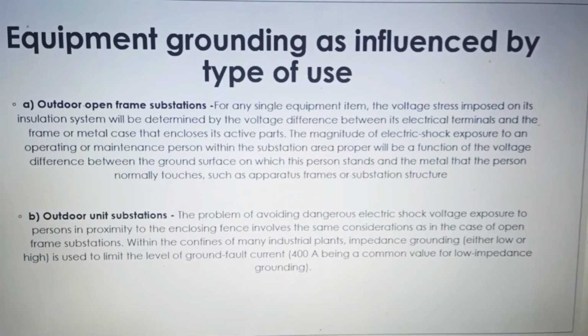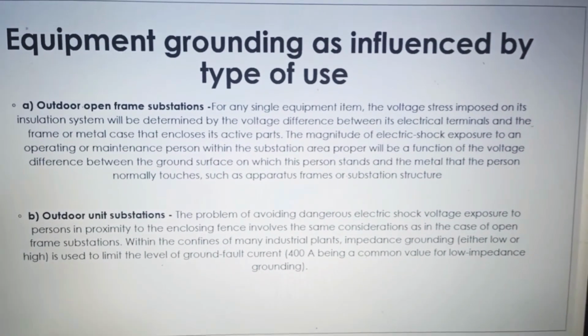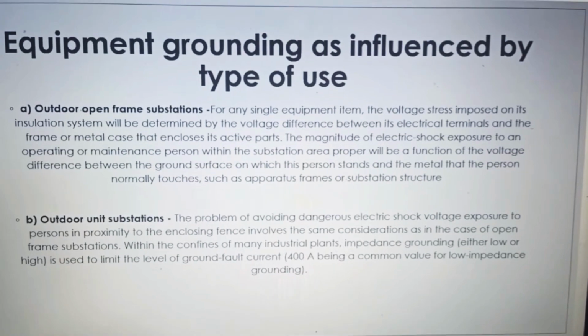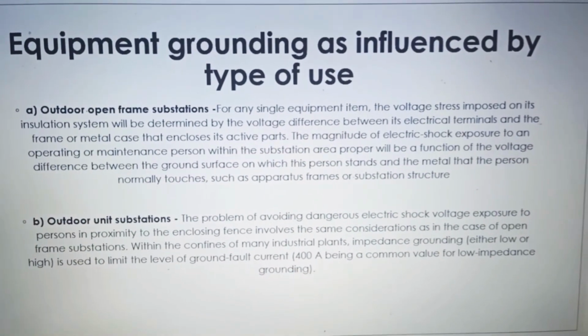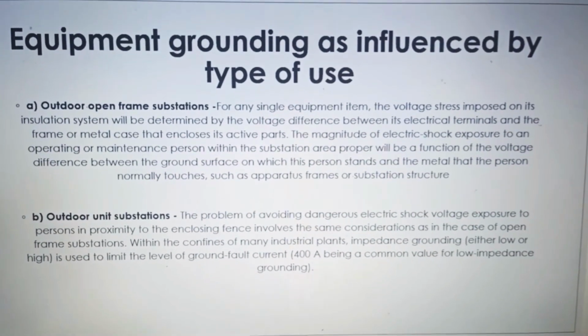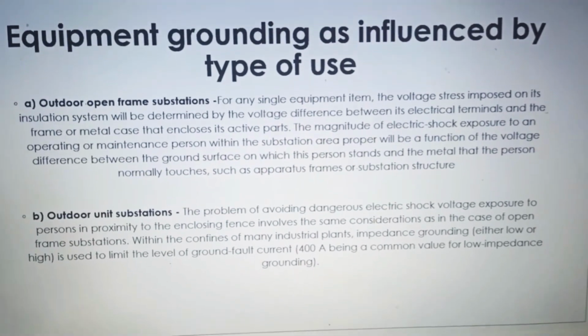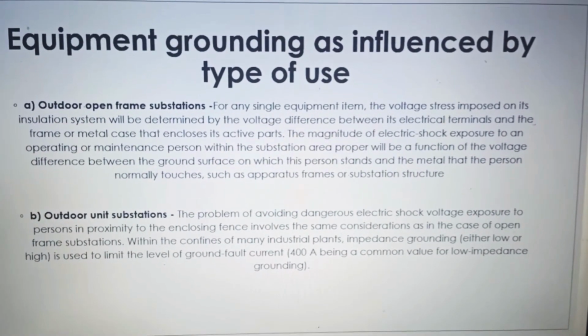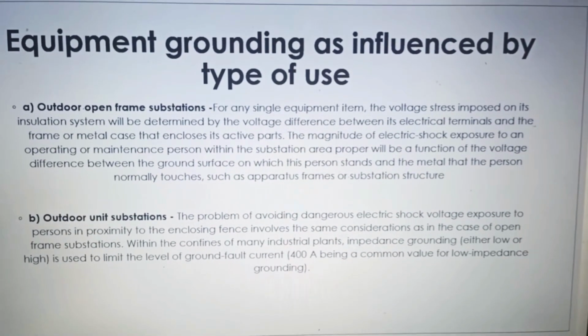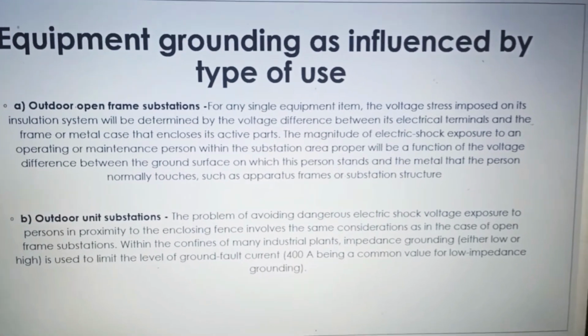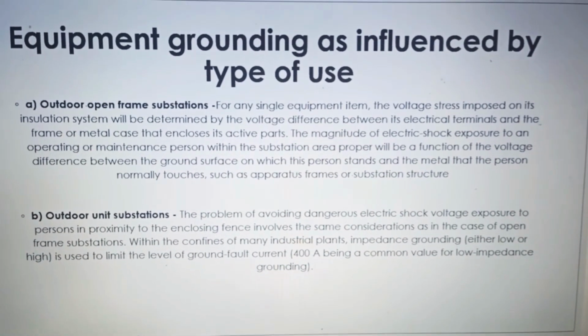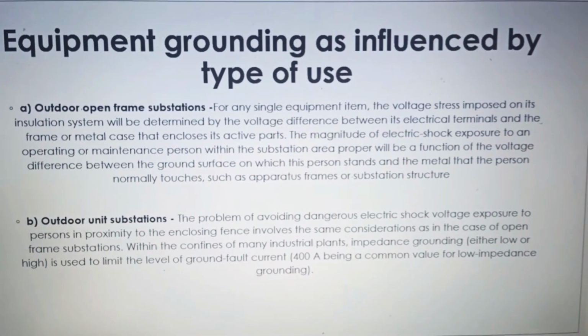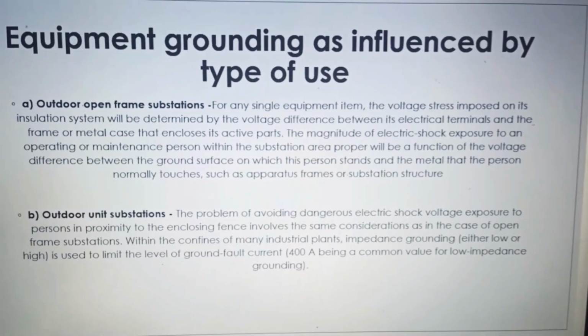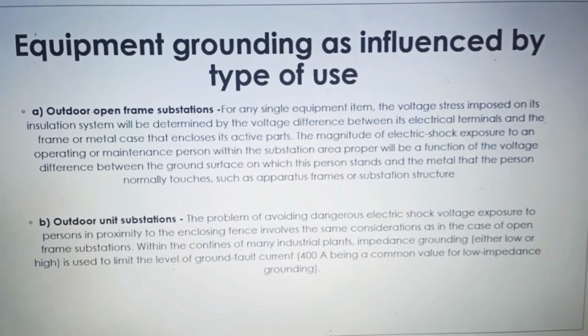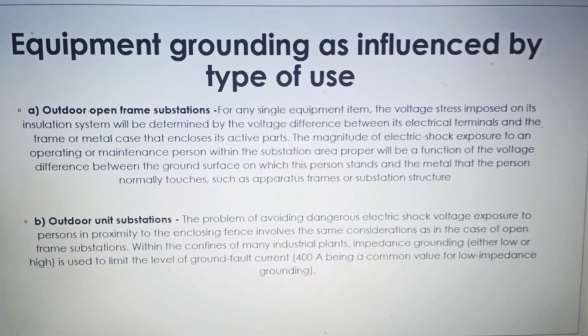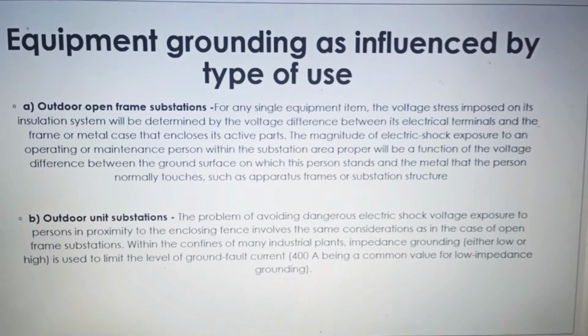It is common that various pieces of major apparatus will be found as island installations within the substation area. For any single equipment item, the voltage stress imposed on the insulation system will be determined by the voltage difference between its electrical terminal and the frame, or the metal case that encloses its active part. The magnitude of the electric shock exposure to an operating or maintenance person within the substation area will be a function of the voltage difference between the ground surface on which this person stands and the metal that the person normally touches. The magnitude of electric shock voltage exposure to a person approaching a fence will depend on the character of the surface voltage gradient contour adjacent to the fence on the outside of the substation area.